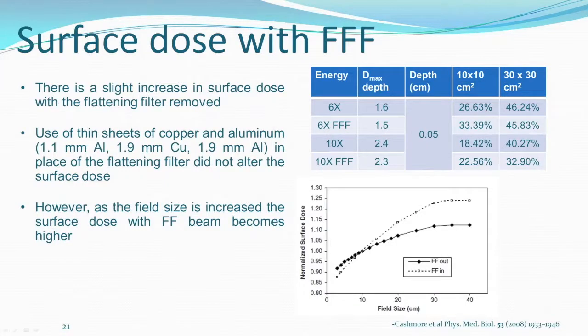Let us look at the surface dose. There is a slight increase in the surface dose when you remove the flattening filter, particularly if you're working with a narrow beam, because you have a soft beam. The soft beam will bring in, you know, more surface dose because of more low energy X-ray components. So you will have more surface dose. But as you increase the field size, what happens is your surface dose doesn't increase very much for FFF, but increases a lot for flattened beams.